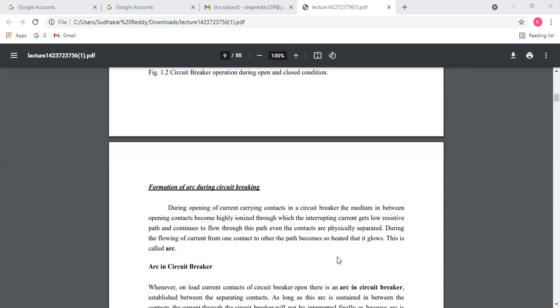Whenever the current carrying contacts of the circuit breaker open on load, an arc is established between the separating contacts. As long as the arc is sustained between the contacts, the current through the circuit breaker will not be interrupted, because the arc is itself a conductive path of electricity. For total interruption of current, it is essential for the circuit breaker to quench the arc. The main design criterion of a circuit breaker is to provide appropriate arc quenching technology for quick and safe current interruption. Before going through the different arc quenching techniques applied in circuit breakers, we should try to understand what an arc is, the basic theory of the circuit breaker.